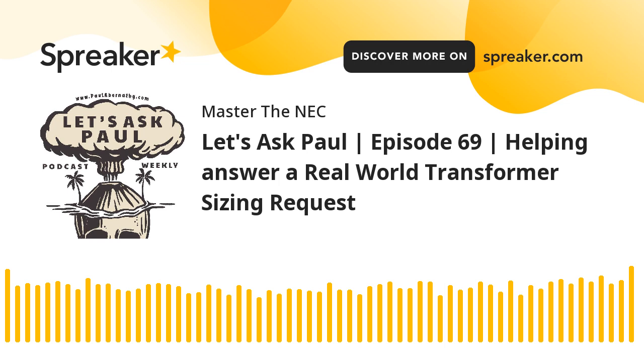Now, the beautiful thing about this is you're not limited in those secondary conductors' length because it's outside. You have conditions you have to meet, and how it's terminated and what have you, but you don't have a length. It's not like the 10-foot secondary conductor rule or the 25-foot secondary conductor rule, because you're outside for all of this, okay? So let's look at that.